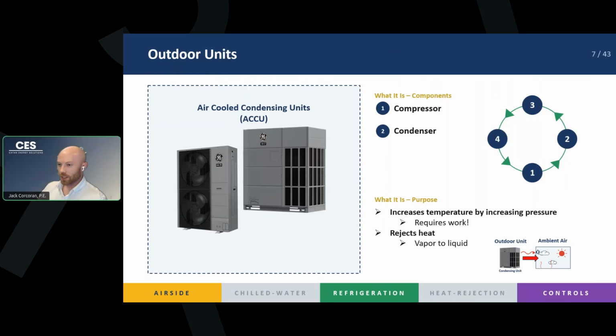So looking at our outdoor units, where do they fit in our refrigeration cycle? It's components 1 and 2, right? It's our compressor and our condenser. This portion of the refrigeration cycle, as we recall, is adding in the pressure. Our compressor does the work to increase the pressure and the temperature so that we can reject heat to the ambient air. These are sometimes called air-cooled condensing units, so you'll see them on drawings with the tag ACCU. That's because air-cooled is the medium we're transferring the heat to outside, and a condensing unit is just the type of equipment it is. So at a high level, we're looking at components 1 and 2 in our refrigeration cycle with our outdoor units.